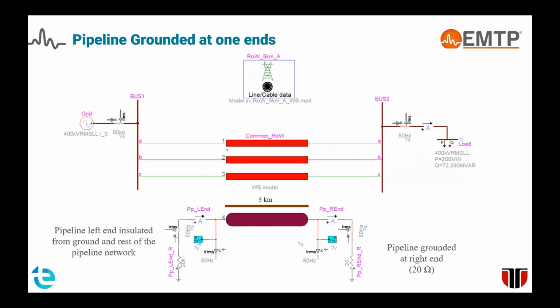In order to present the most important parameters that affect induced voltages and currents in metallic pipelines next to high voltage power lines, we consider a reference case with a not so ideal insulation of the pipeline, considering a more realistic resistance of the insulation coating, a 20 kilo ohm resistance for our system.